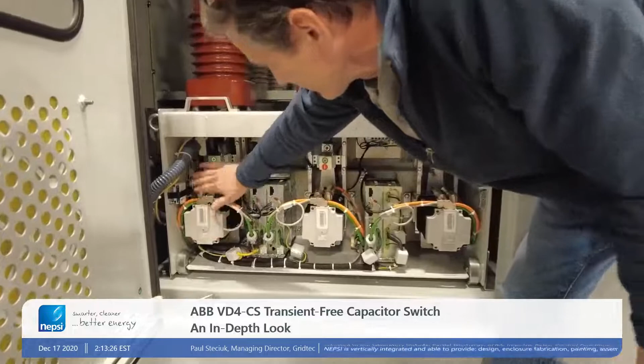No. What you're looking at here are three servo motors — one for phase A, one for phase B, and one for phase C. Each of these servo motors is driven by a CPU card: a card here for this servo motor, a card for this one, and a card for this one. Then there's a CPU for overall operation of the VD4. One thing you'll note is this is built with a lot of quality — there are basically military connectors everywhere, and it's a very well built breaker.